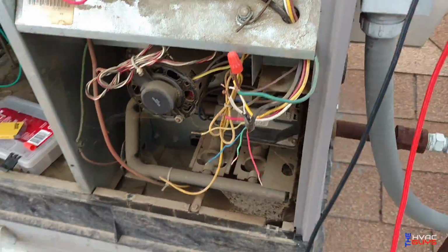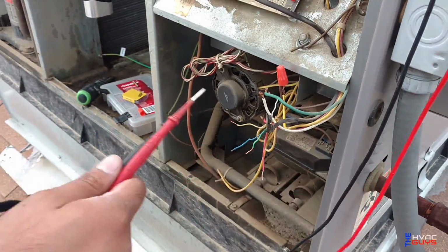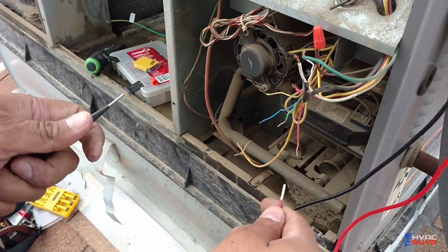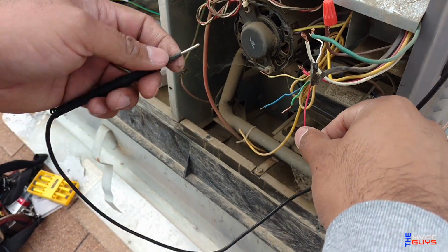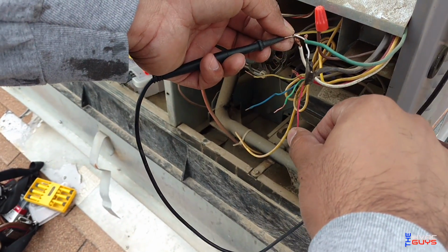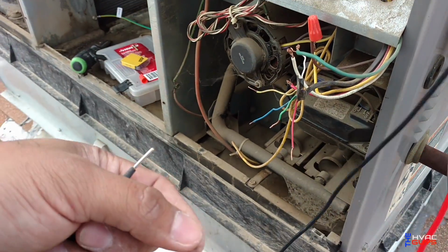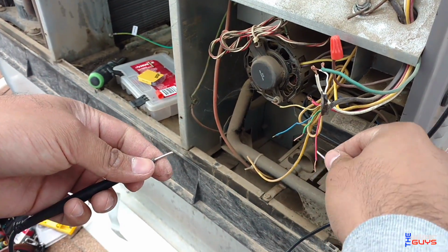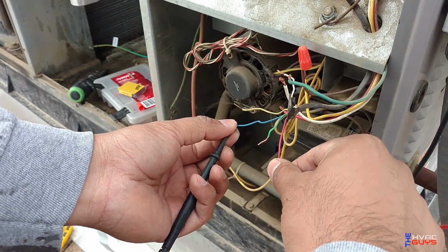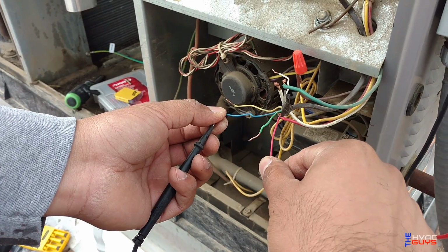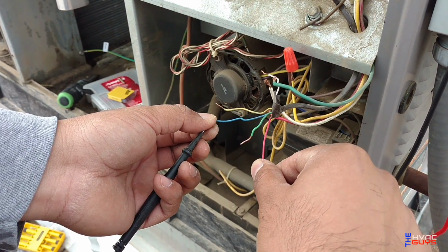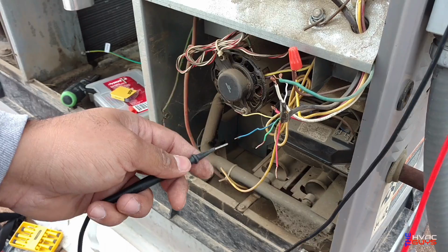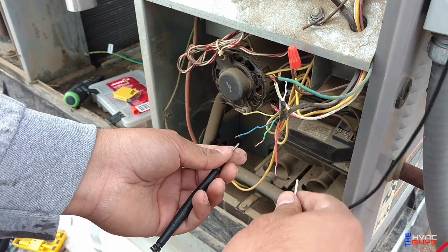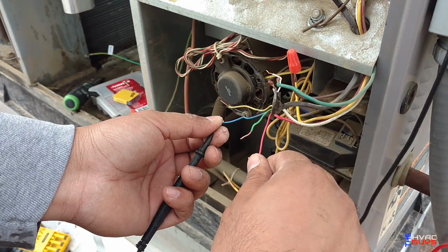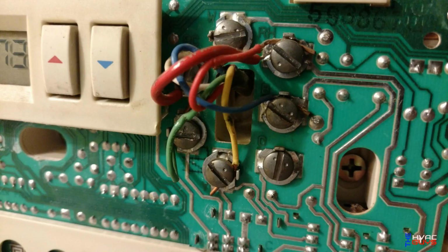So we just eliminated the thermostat wire from the unit's low voltage wires. From red to white, we do have continuity because the thermostat is on. From red to blue, we're not supposed to, but you see how it is. So I'm guessing that blue wire is touching some type of ground somewhere, and that's what's causing our fuse to blow.